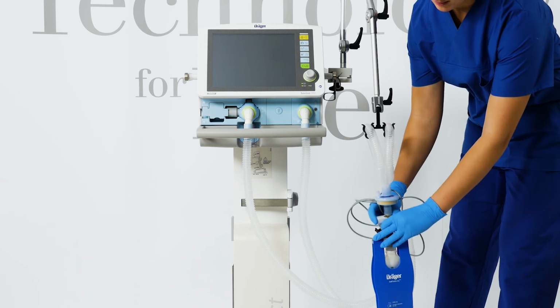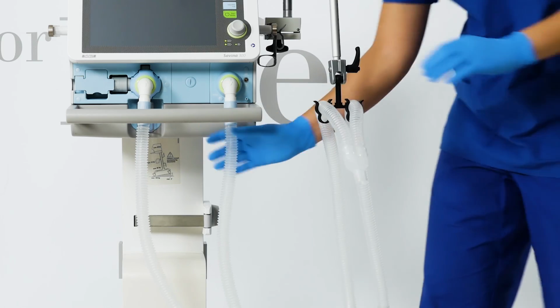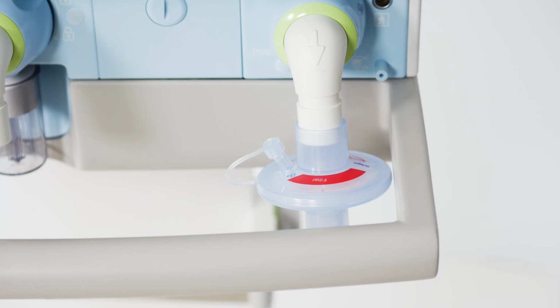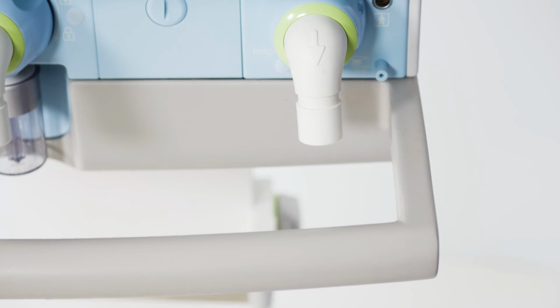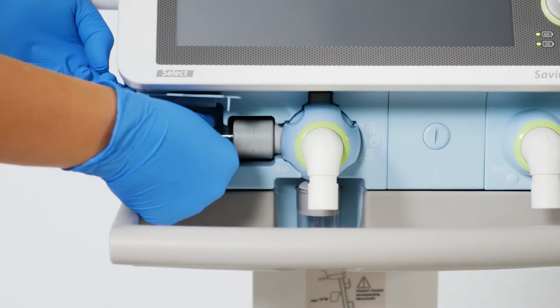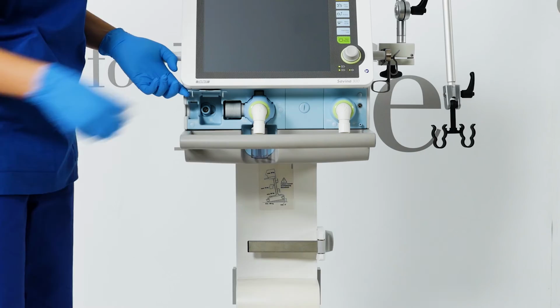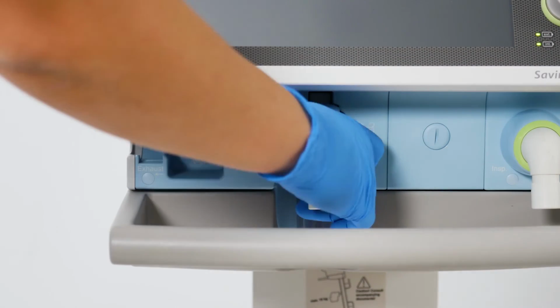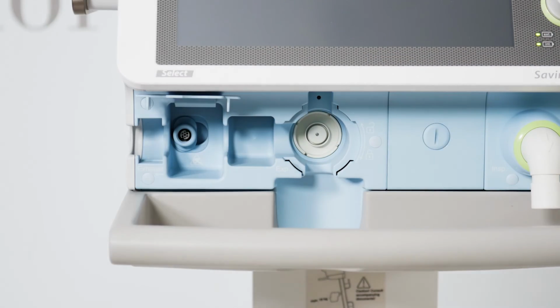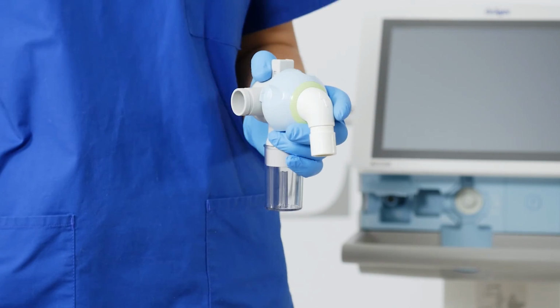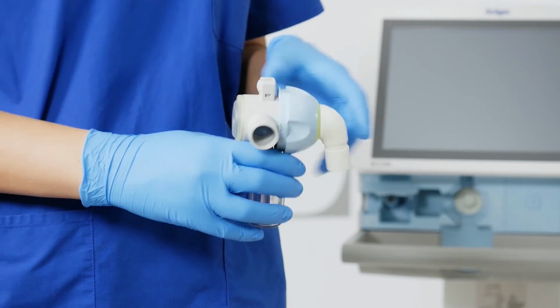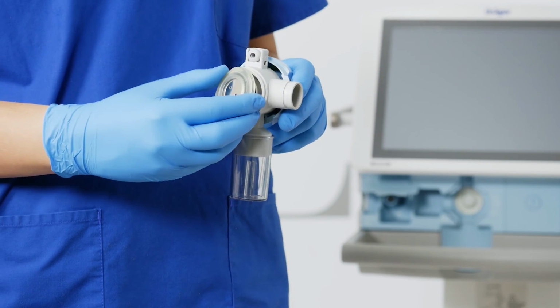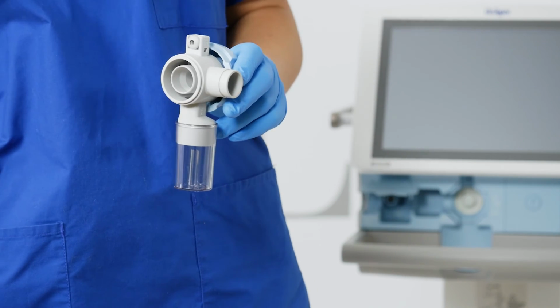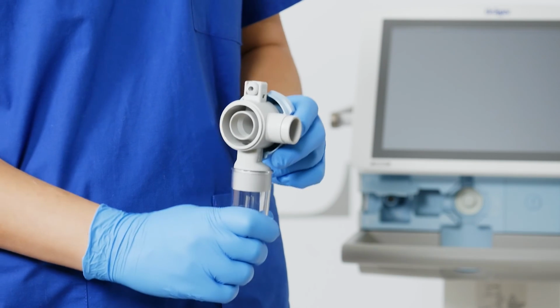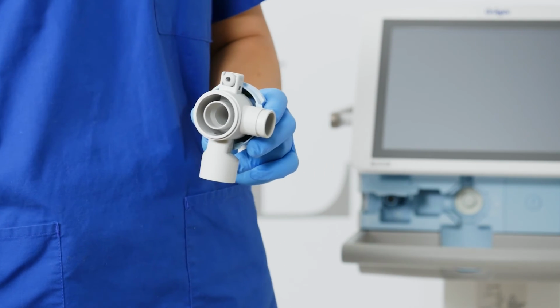Now remove the CO2 sensor, the breathing hoses, the bacterial filter, the flow sensor, and the expiratory valve. Pull the flow sensor sleeve from the expiratory valve and remove the diaphragm. Remove and empty the water trap container.